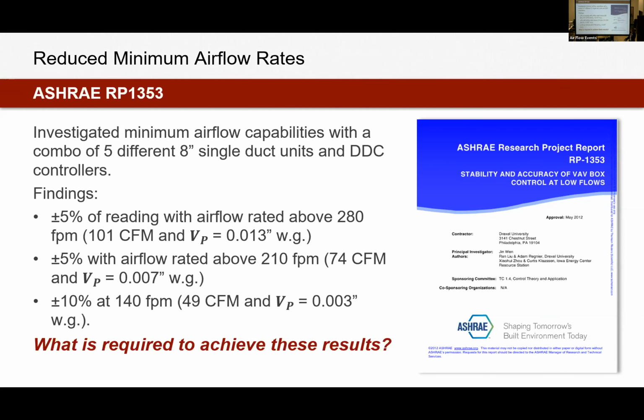And what they ultimately found in this research report, the whole point of the study was to figure out, can we actually turn down boxes below current manufacturer's minimums? What they found is yes, you can. You could turn down pretty far. So here we've got an example of turning down to 101 CFM, turning down to 74 CFM, and even 49 CFM. So really, really lows.